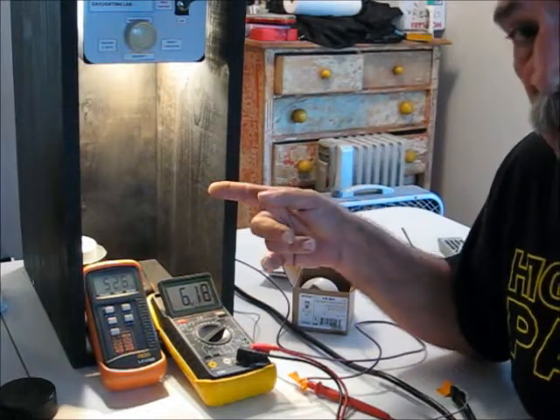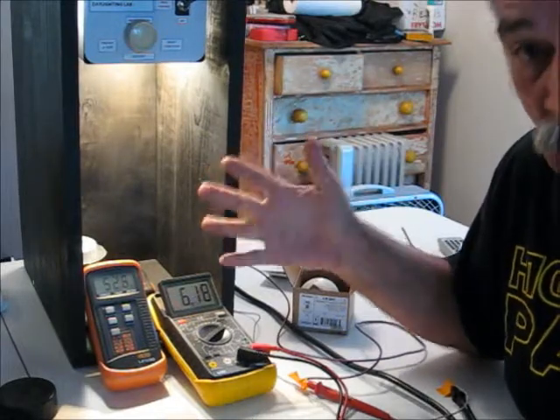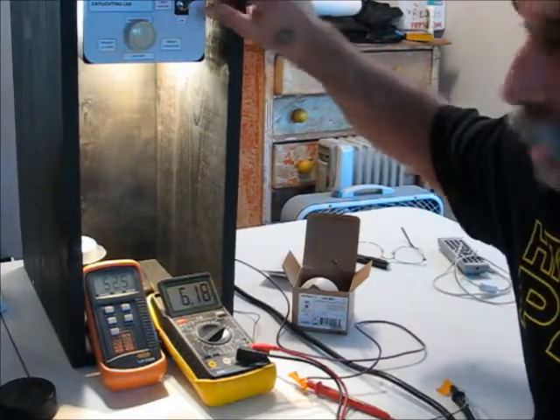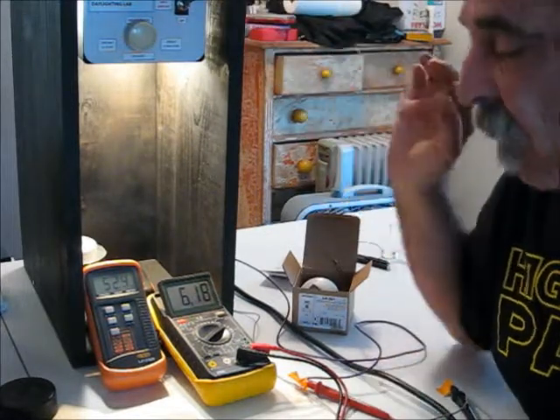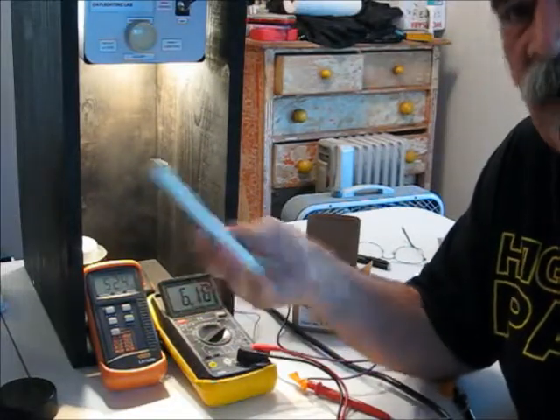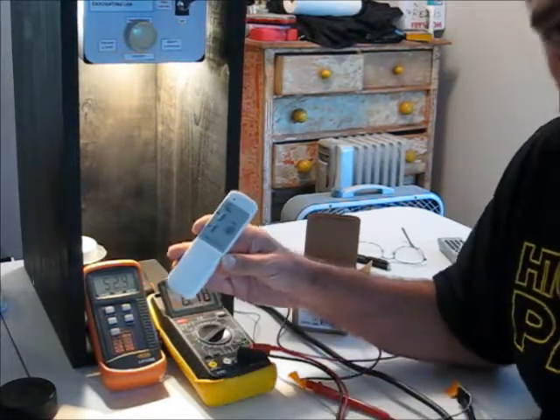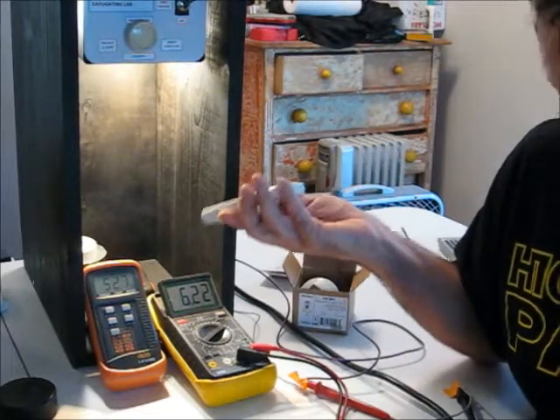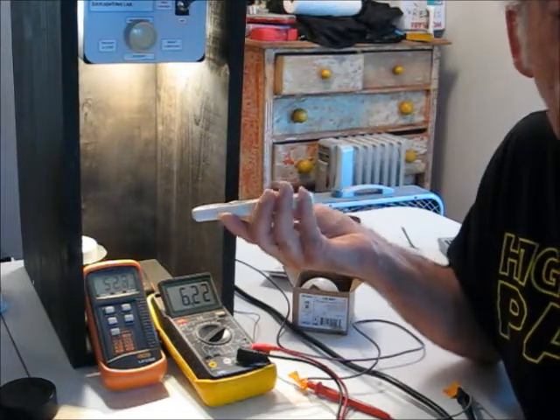If I am in an area under the 2013 or 2016 code that does not require multi-level control but might still require daylighting, good to go with just a toggle switch, and maybe the healthiest way to go with this. However, if I'm in an area that requires multi-level controls, it's over 100 square feet, etc., this unit comes with a personal remote that can be used to dim it up and down.